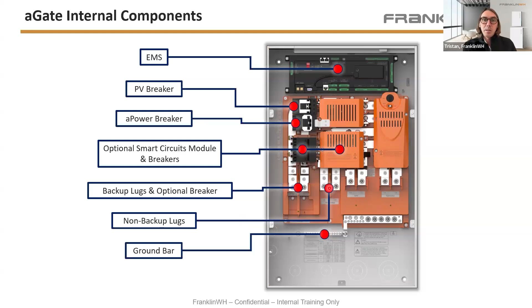Thank you. We can go to, well, I want to just point out the backup lugs and the optional breakers. So we have non-backup lugs and backup lugs. Those are all rated for 200 amps. So the backup lugs are going to be your distribution, all of the circuits that are going to be connected and energized in an off-grid scenario. And then the non-backup lugs are going to be the circuits that, for whatever reason, the homeowner or installer may choose to be excluded during an off-grid scenario. So those would be de-energized and not available to the homeowner. We go to the next slide, please, Dave.